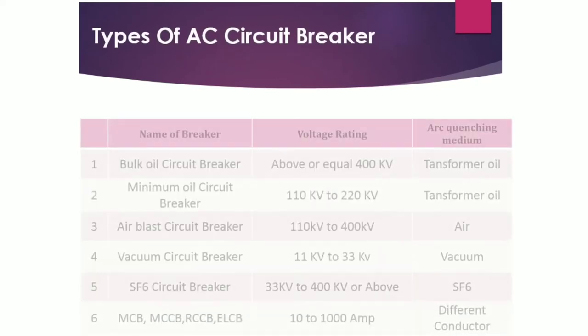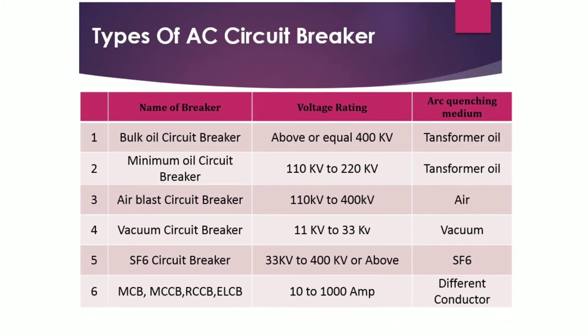There are six types of circuit breakers in common application. First, the bulk oil circuit breaker, rated at above or equal to 400 kV, using transformer oil as the arc-quenching medium. Second, the minimum oil circuit breaker, with a voltage level of 110 kV to 220 kV, also using transformer oil as the arc-quenching medium.